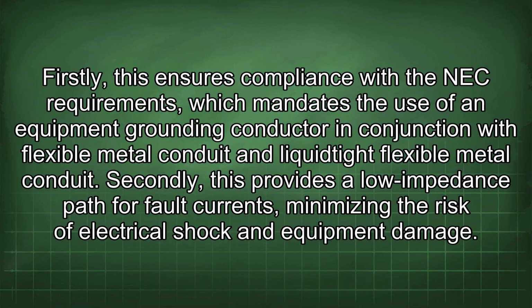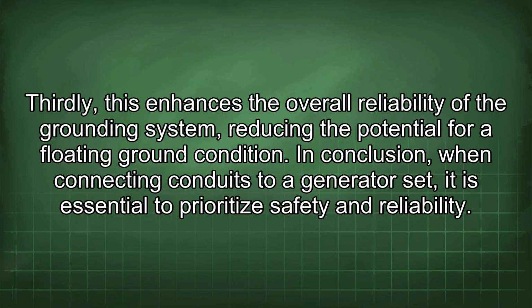Firstly, this ensures compliance with the NEC requirements, which mandates the use of an equipment grounding conductor in conjunction with flexible metal conduit and liquid-tight flexible metal conduits. Secondly, this provides a low impedance path for fault currents, minimizing the risk of electrical shock and equipment damage. Thirdly, this enhances the overall reliability of the grounding system, reducing the potential for a floating ground condition.